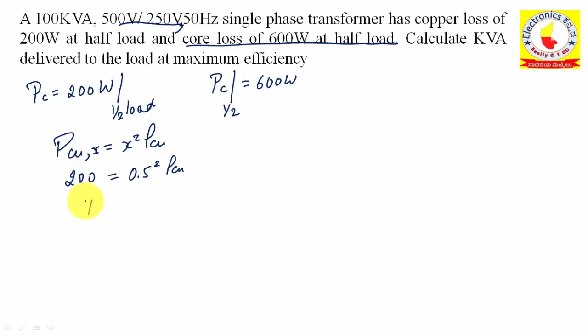We know that PCU of x equals x square times of PCU. They have given this value as 200, which equals what? The value of x square at half load is 0.5 square times of PCU. So what is the value of copper loss you are going to get? 800 watts you are going to get.